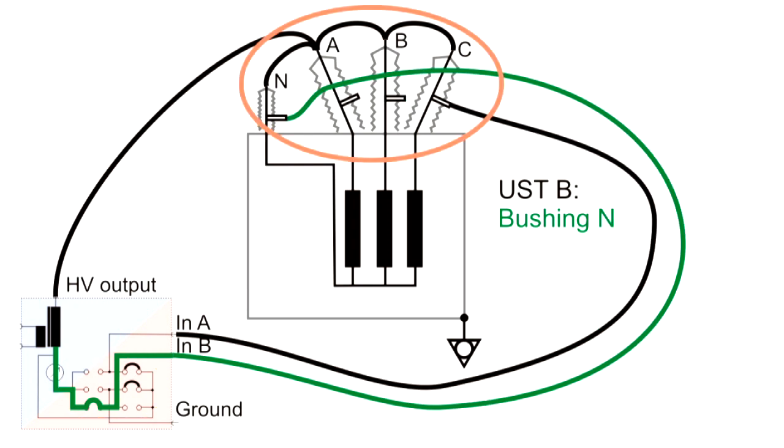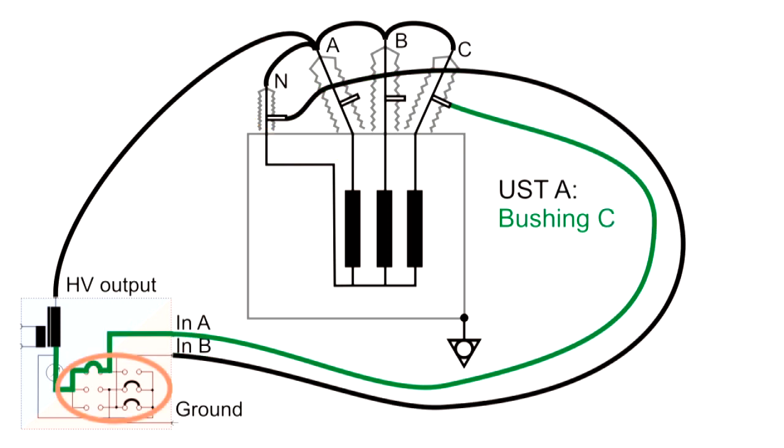Now we must reconnect the test leads once to measure bushings N and C. With USTB mode set in the test card, the test leads are now connected to bushing N. The next test card uses mode USTA to connect to bushing C, again without the need for any rewiring.